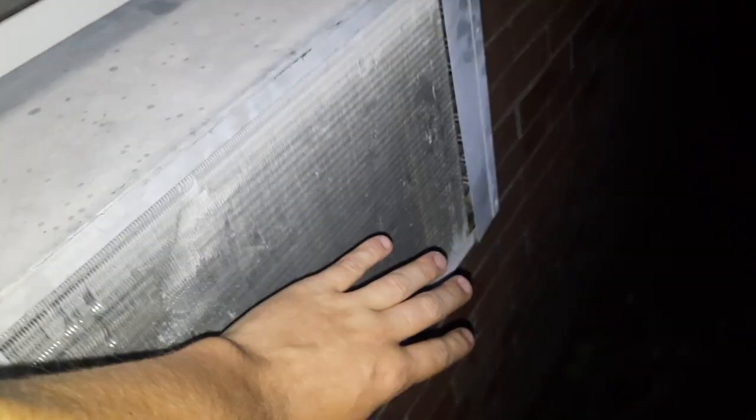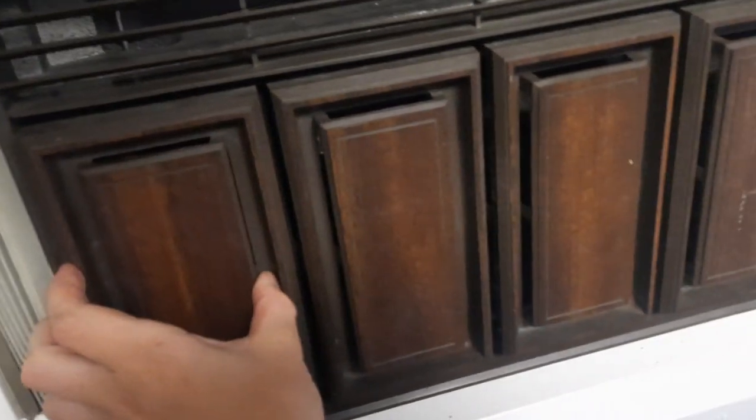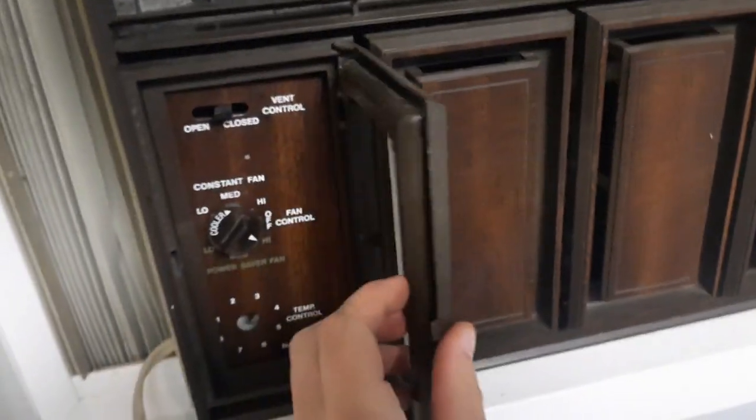It's running really good. I had the coil on this thing cleaned out too — I worked on this one earlier this season. The next thing I want to test is the fan motor: is it still locked up like it was before, where it just didn't want to start up again on low speed? I don't hear any bad scratching noises, so I think it's just the bearings are dirty.